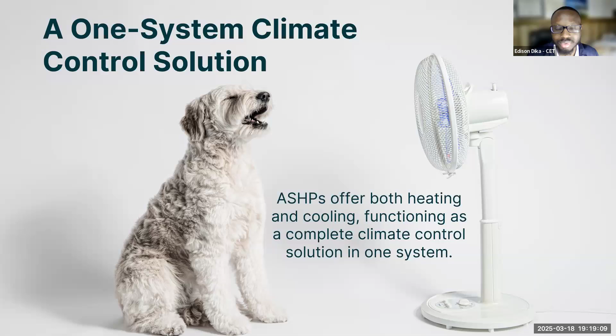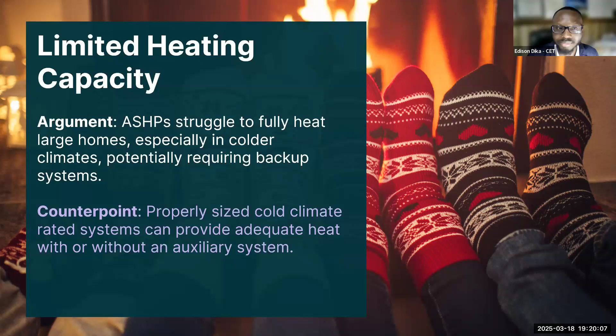We'll go through some common criticisms and their counterpoints. Some folks say heat pumps have limited capacity, arguing they struggle to fully heat large homes, especially in colder climates, potentially requiring backup systems. The counterpoint is that properly sizing a cold-climate-rated system can provide adequate heat with or without auxiliary systems. Performing a good Manual J load calculation plays a key part in making sure the heat pump can meet the home's heating load.